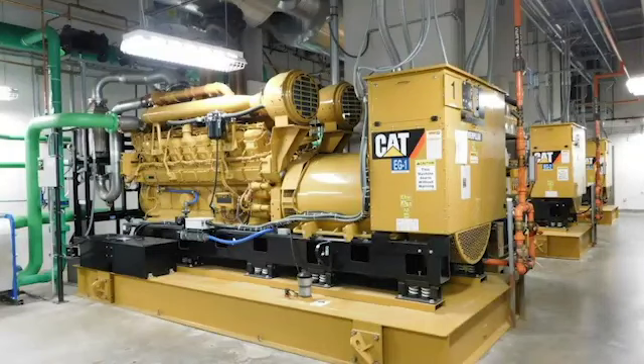We'll walk into the emergency diesel generator room itself, where we have these three CAT 3516 diesel engines, each good for a full 2 megawatts of power. The hospital load is only about 2 megawatts, so we're actually in N+2 right now, but we're ready for a little bit of future growth if the hospital decides to add any additional floors or any additional buildings to their campus. We could handle that without any big changes.